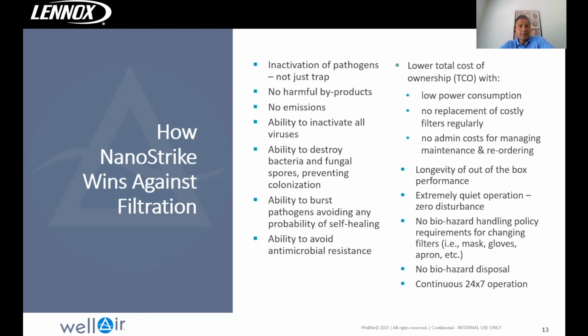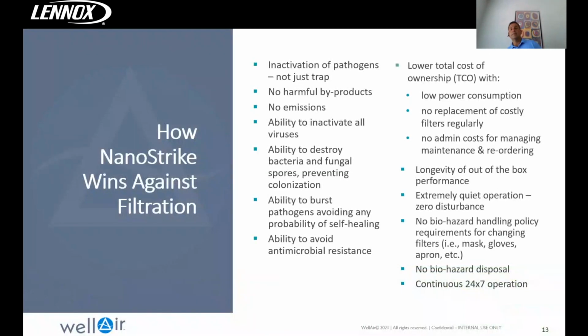The other challenge with HEPA filters is where you locate them. The airflow needed to get to the HEPA filter may allow viral elements in the air to come in contact with a person. Think about it: if you're in a school with a portable HEPA filtration unit, and I'm standing here, and somebody sick is in front of me, the airflow going back to that unit will carry that virus-filled air through my face before it goes into the HEPA unit. So I will get sick. Yes, the virus will get caught eventually, but you're exposing people to a virus or other transmissible element because you're not destroying it or deactivating it.